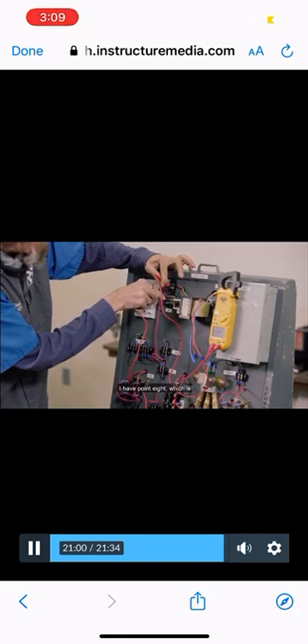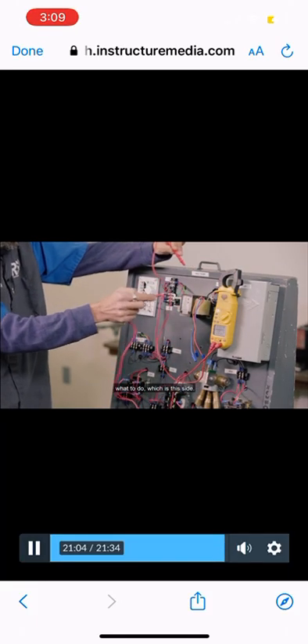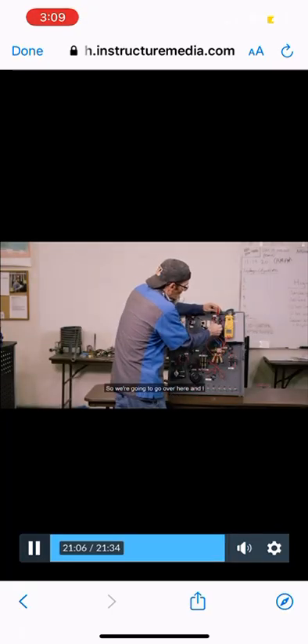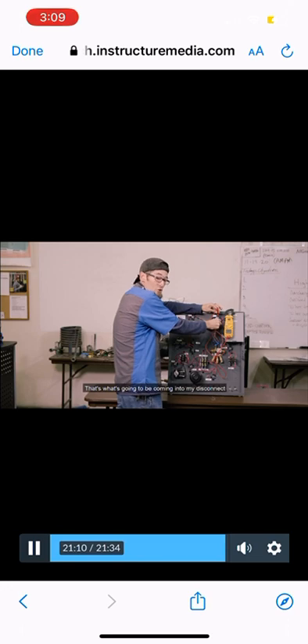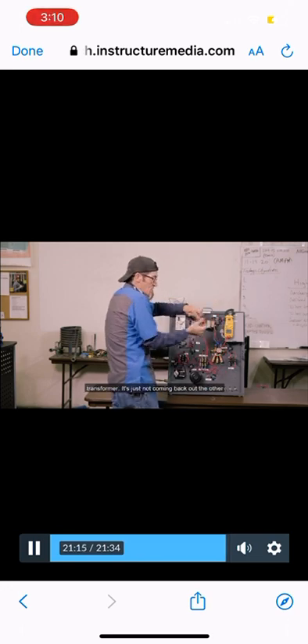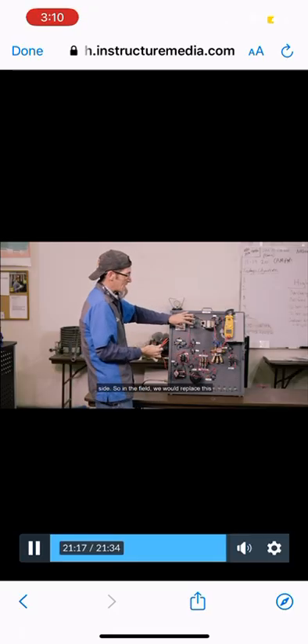I have 0.8, which is basically 0. So I'm going to look at who tells it what to do, which is this side. So we're going to go over here. And I have 120 volts, which I should. That's what's going to be coming into my disconnect over here. So I'm getting the high voltage into this transformer. It's just not coming back out the other side.